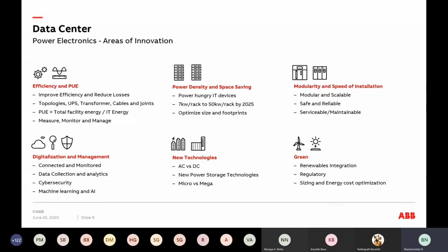Typically for data center power, the measure used is PUE, the total facility energy divided by the IT energy. That means, at the end of the day, the power has to be utilized by the IT infrastructure, your servers. So to deliver that power, how much energy are we wasting versus actually consuming at the input side? In the transformation, whether in the UPS, storage, transformer, or cables, how much energy are we losing? Our goal is to reduce losses as much as possible and work towards bettering PUE, and we're also working on solutions in the areas of measure, monitor and manage to further increase efficiency.